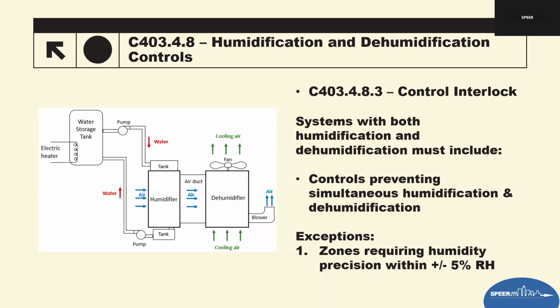So simultaneous operation is both wasteful and a sign of poorly configured controls. Back to, you got cities now requiring commissioning. These type of interlocks would be on a commissioning list to verify that they actually meet the requirement. There are exceptions for the interlock though.